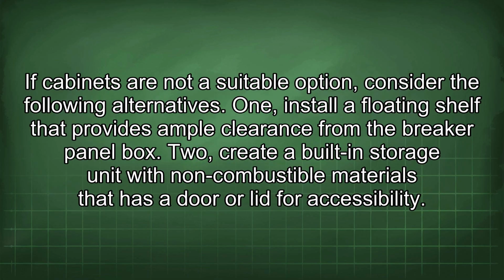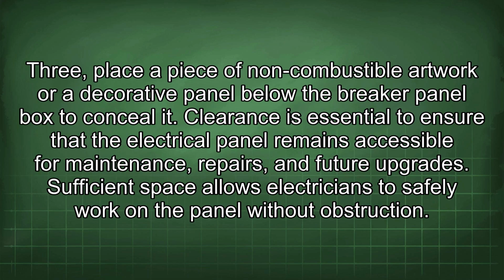If cabinets are not a suitable option, consider the following alternatives. 1. Install a floating shelf that provides ample clearance from the breaker panel box. 2. Create a built-in storage unit with non-combustible materials that has a door or lid for accessibility. 3. Place a piece of non-combustible artwork or a decorative panel below the breaker panel box to conceal it.